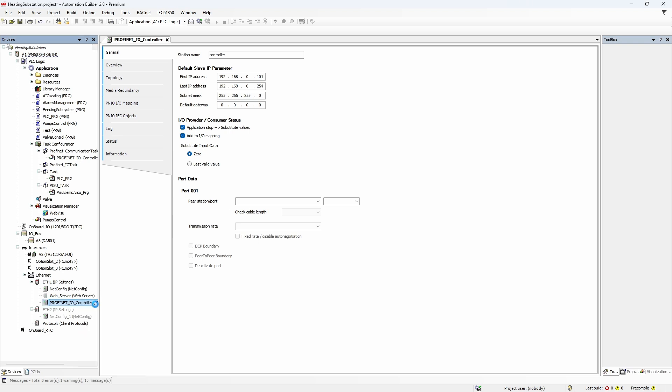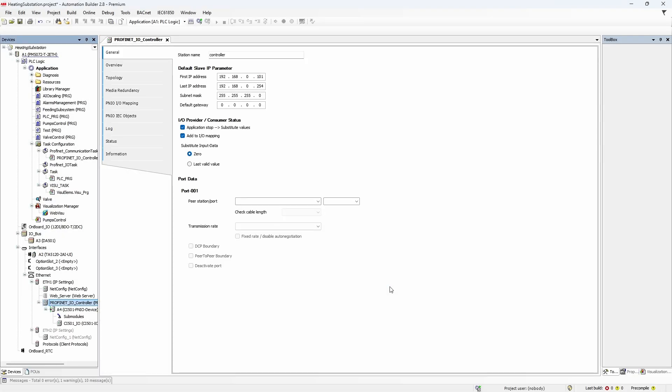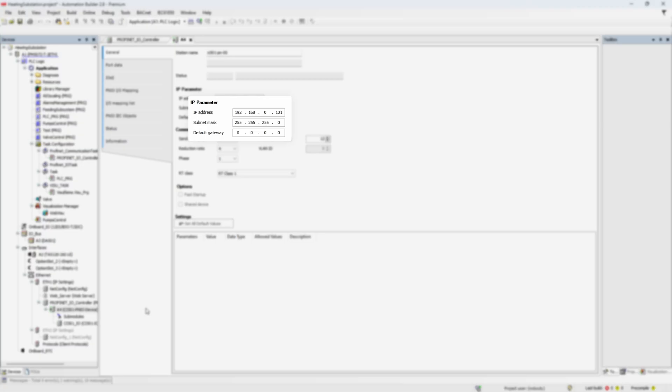Now, under PROFINET I.O. controller, add the PROFINET I.O. device. In the section communication interface modules, you will find CI501 device. Give it a name which corresponds to electrical drawings and hit add object. Go to settings of the added device. You can see that IP address is already set from the range we specified before.